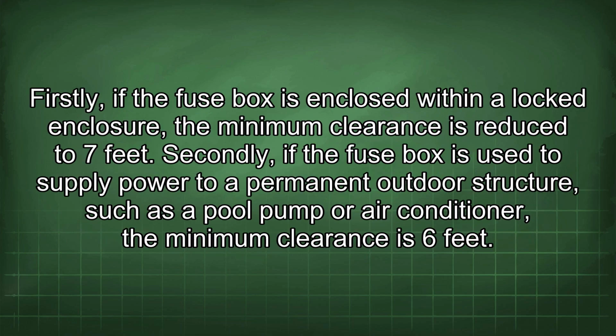Firstly, if the fuse box is enclosed within a locked enclosure, the minimum clearance is reduced to 7 feet. Secondly, if the fuse box is used to supply power to a permanent outdoor structure such as a pool pump or air conditioner, the minimum clearance is 6 feet.